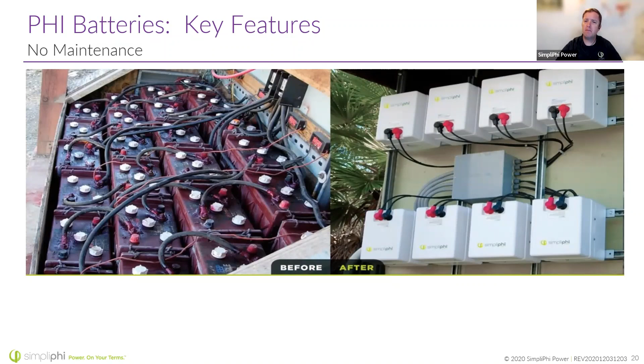So I'm going to jump into some products before we start installation. This is our best seller, the PHI 3.8 kilowatt hour battery, 151 amp hours at 24 volts, or 75 amp hours at 48 volts. I want to take a moment to say you never want to run our batteries in series, always in parallel. So if you've got a 48 volt system, buy 48 volt batteries. You never want to buy our 24 volt batteries and run them in series. Again, simple parallel connections let us scale up to the size system we need.